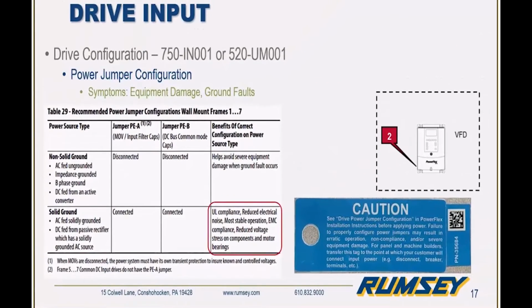Failure to do this can result in actual damage to the drive or ground faults occurring. So it's really critical that this is taken into account. And oftentimes it's overlooked because it's not really easily seen. In fact, Rockwell has gone to the trouble here to ship the drives with a sticker that specifically states to confirm the position of these power jumpers prior to powering up the drive. So again, another critical aspect here, making sure we have the drives configured correctly for the install.